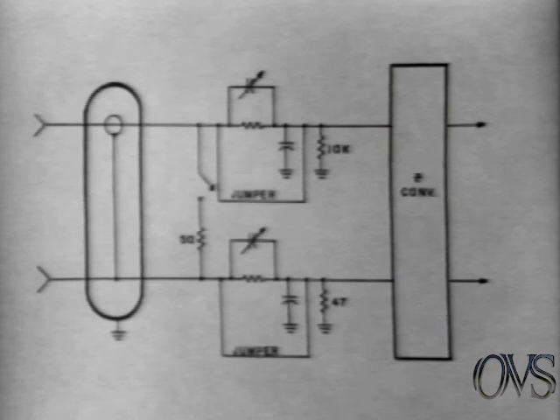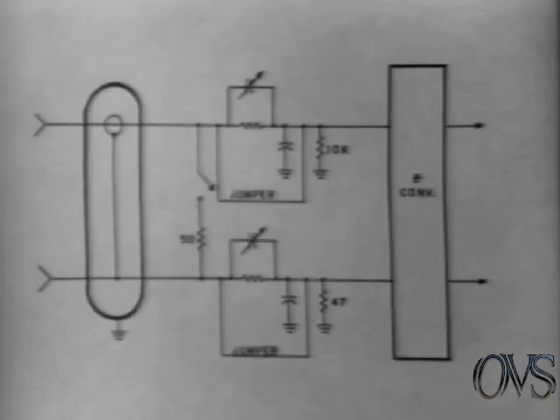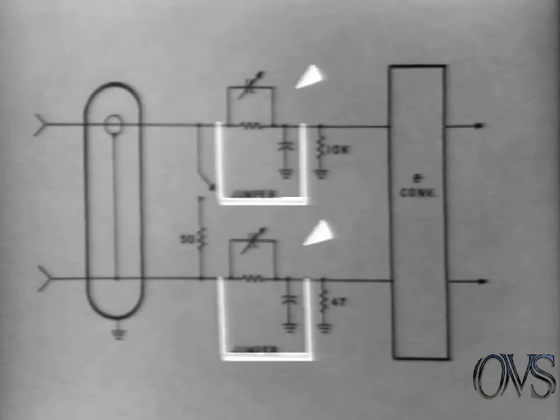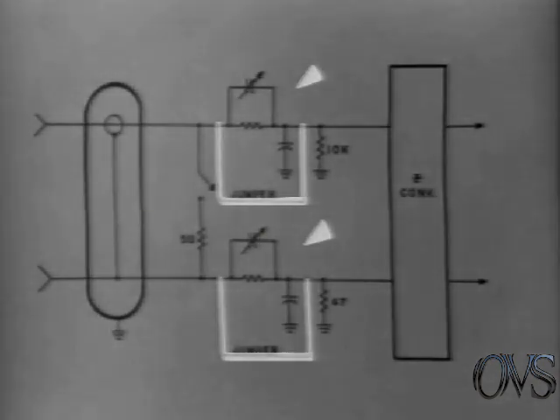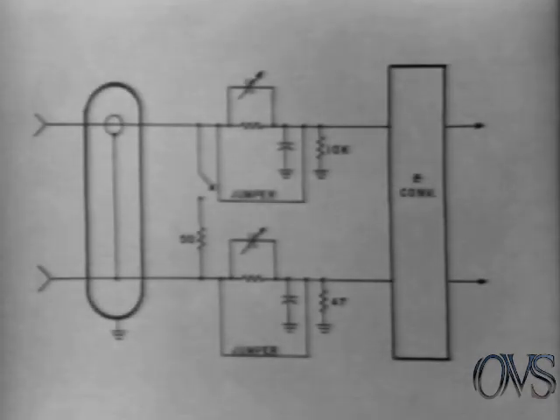Instruments are shipped in a single-ended configuration, but are easily changed to differential operation by changing this resistor value from 47 ohms to 10 k ohms. X and Y deflection factors can be varied by removing these jumpers and changing these resistor and capacitor values. Section 3 of the Operating and Service Manual provides complete instructions for these modifications. Input impedance can be switched between 10 k ohms and 50 ohms with this switch. Here's where the switches are located on the X and Y axis input amplifier boards.